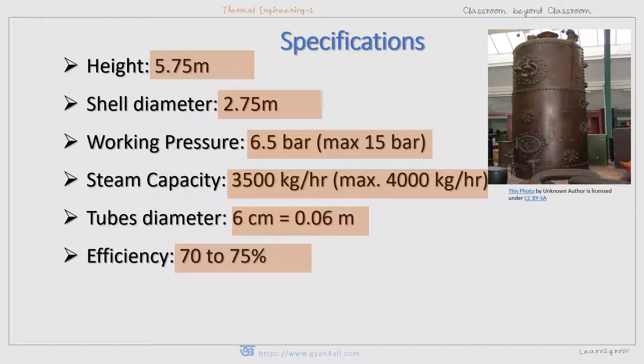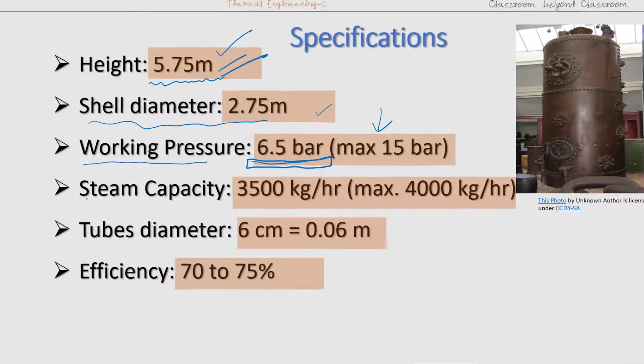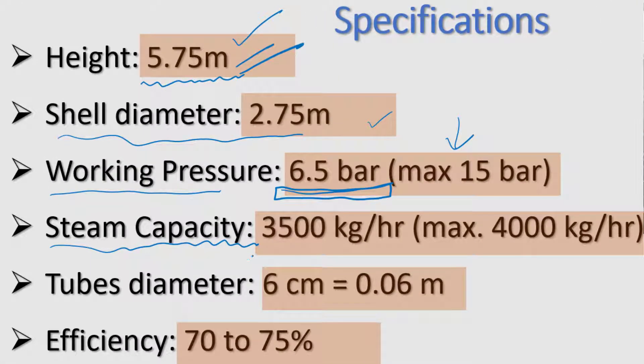Now let us mention some specifications of the Cochrane boiler. Specifications may vary depending upon requirements and specific applications. Generally, the height of the Cochrane boiler is 5.75 meters. The diameter of the shell is 2.75 meters and the working pressure is 6.5 bar, which is why it is called a low pressure boiler — it may go up to 15 bar. The steam production capacity is 3,500 kg per hour, and may be increased up to 4,000 kg per hour. The fire tube diameter is generally 6 cm (0.06 m). The efficiency of the Cochrane boiler ranges from 70 to 75 percent.